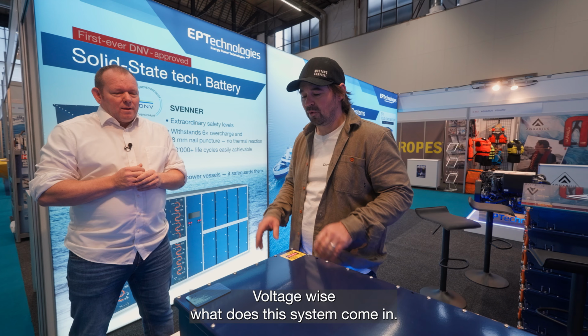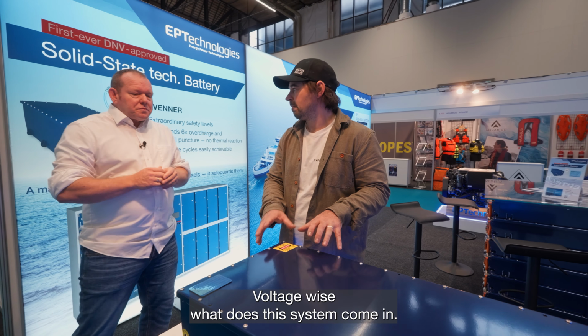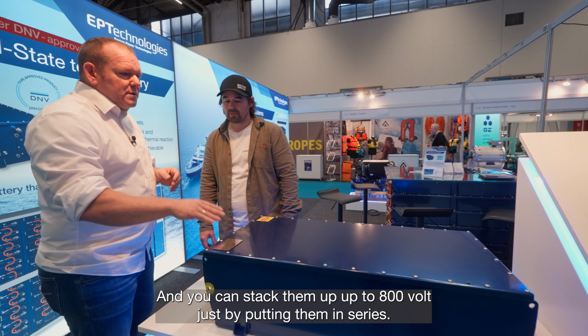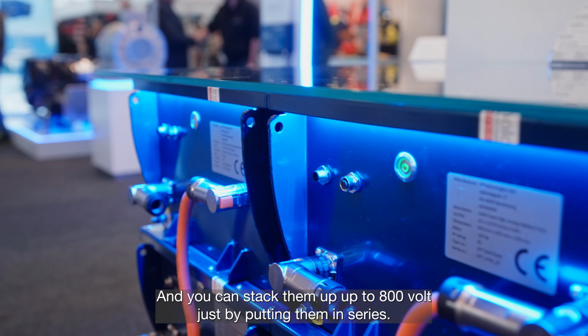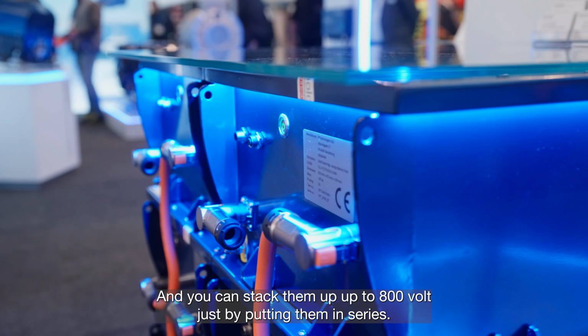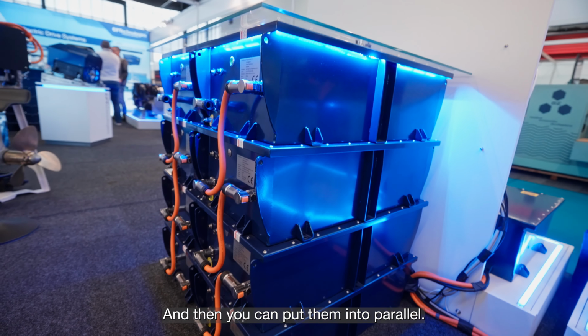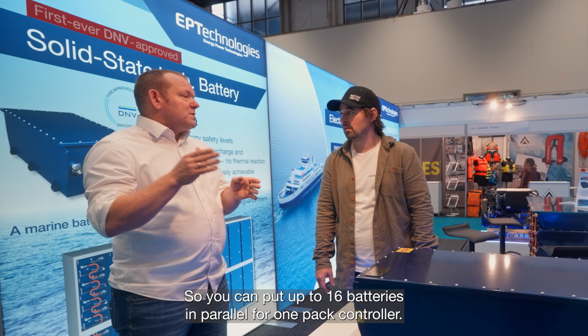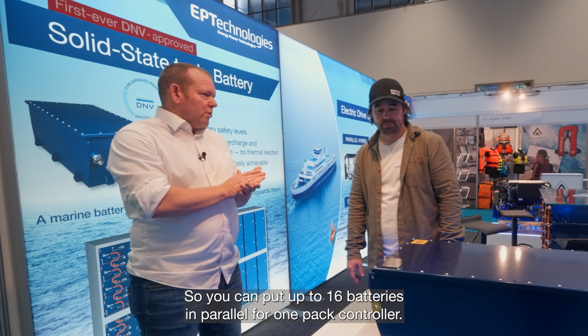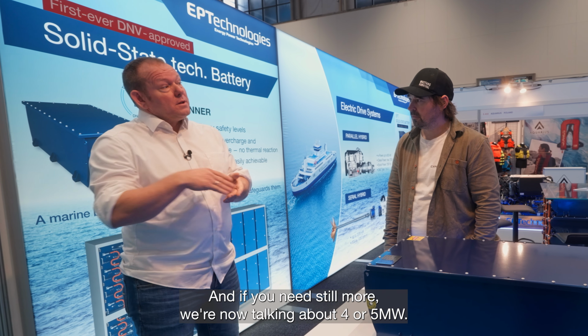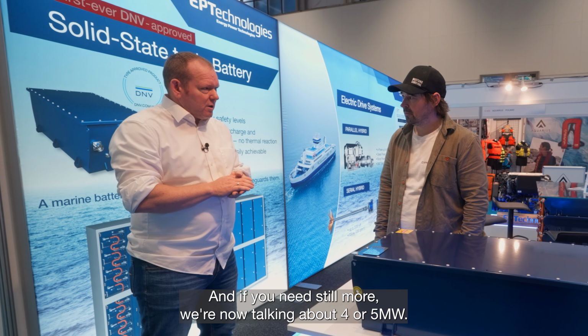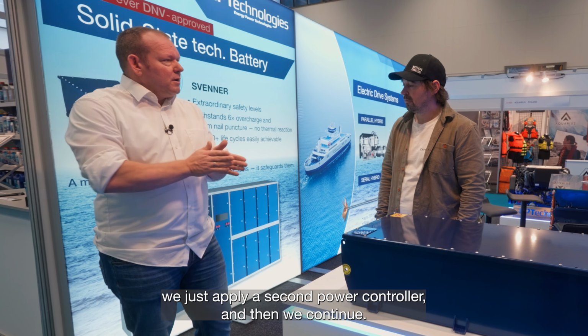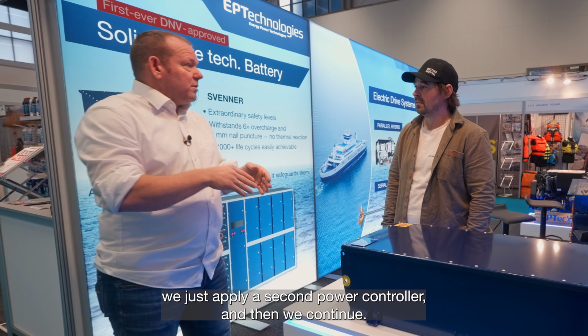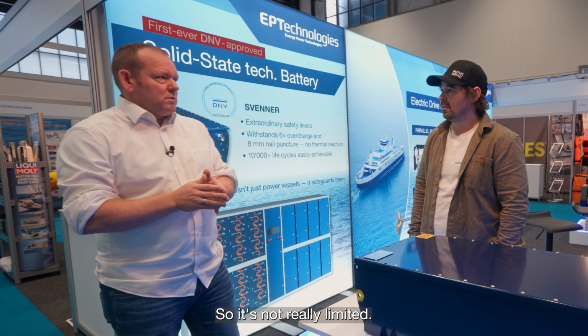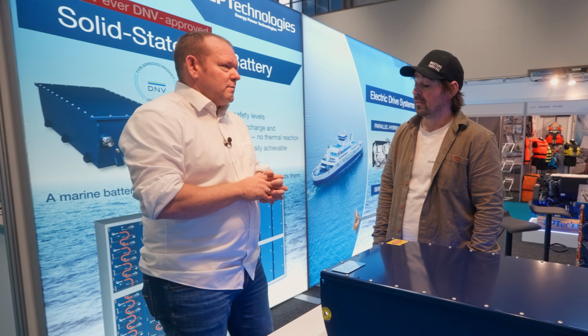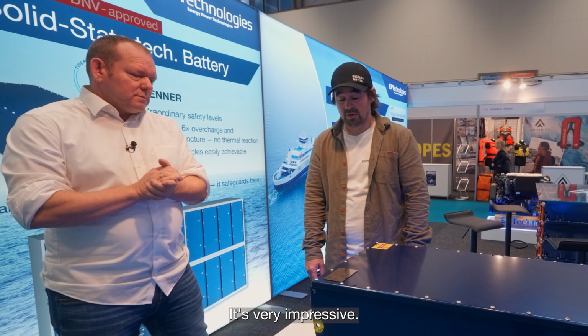Voltage wise, what does this system come in? One module is at 50 volts, and you can stack them up to 800 volts just by putting them in series. Then you can put them into parallel, so up to 16 batteries in parallel for one pack controller. If you need more - we're talking 4 or 5 megawatts - and want 10 megawatts, you just buy a second pack controller and continue. So there's not really a limit.